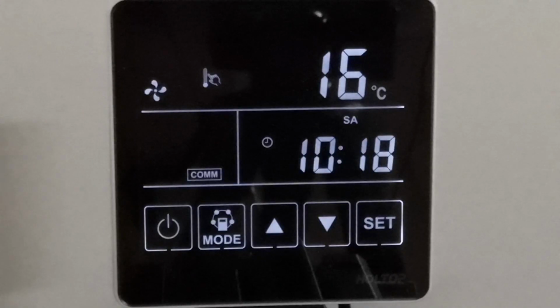Here I would like to point out that the filter alarm signal, if you set filters, can be used for 60 days. So when the ERV runs over 60 days, the filter alarm here will flash to remind you it's time to clean or change the filter. After replacement or cleaning, you can remove the signal by following our user manual instructions, which we'll show you later.